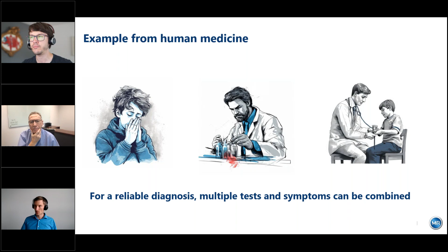This is again a summary of what I just said, but now we are trying to do the same for transformers. If you think about how human medicine works, we usually try to take into account more than one indicator, and we try to do the same with transformers. For example, we can take into account DGA, cooling, oil. We have so many different indicators, and usually if something is faulty, more than one of these indicators can be active. Even if only one of them is active, that is still information we can use. So we try to apply similar diagnostic strategies as in human medicine to get powerful diagnostics for our power transformers.